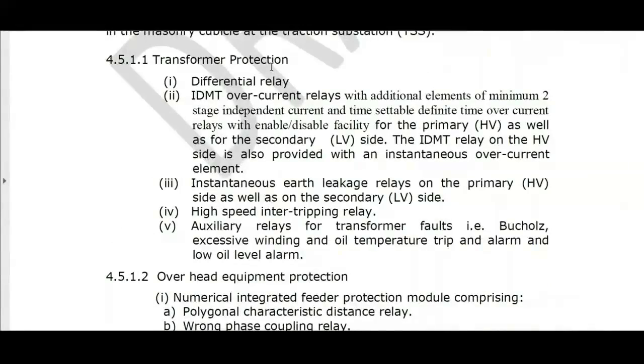A transformer. When you want to protect a transformer, what is the list of protection that you need to provide? These are the 5 protections that you need to provide. Differential relay. This is the same Merz-Price scheme of differential protection or unit protection that we spoke about. IDMT overcurrent relay. IDMT stands for inverse definite minimum time, with 2 independent stages of overcurrent, one for HV and the other for LV. So this is actually the non-directional principle. That is non-unit protection. So the unit protection will provide protection for all the faults which happen inside the transformer.